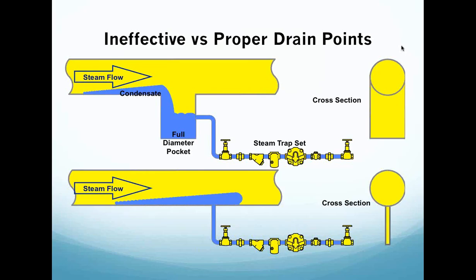In a drain point on a steam main, I wanted you to see this picture. I need you to make sure that you have a full diameter of that steam main being used as an actual condensation collection pot, so that as the condensate forms, we have a steam trap positioned with a full diameter condensate leg, so that we can capture the condensate and then put it back through that strainer and that steam trap. If you don't use the full diameter of that collection leg and you just weld a half coupling on that steam main, that condensate will fly right over the top of that unfortunate orifice that you put in with the intention to collect, but you will have a very difficult time collecting it. Okay, so please make sure that your condensate collection pockets are the size that we need.